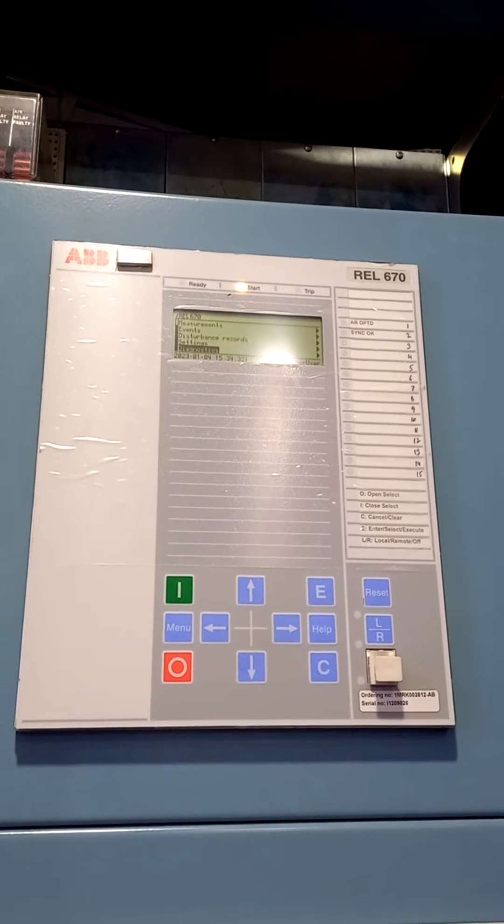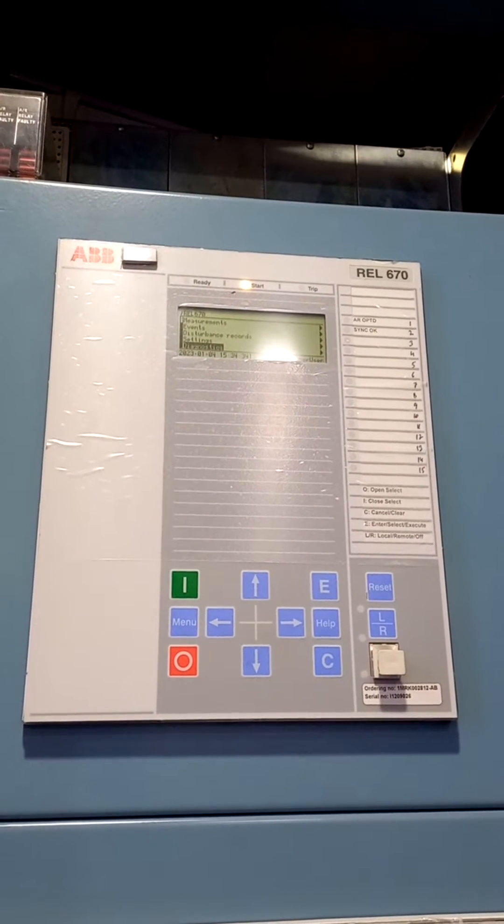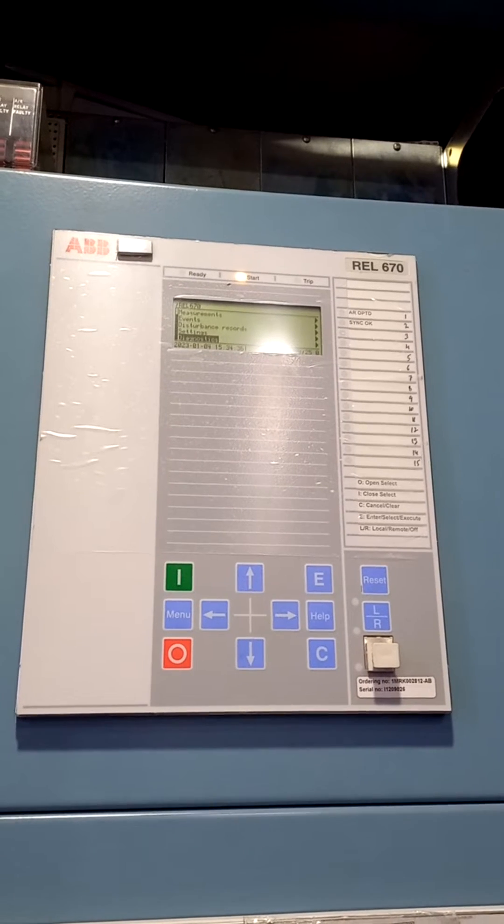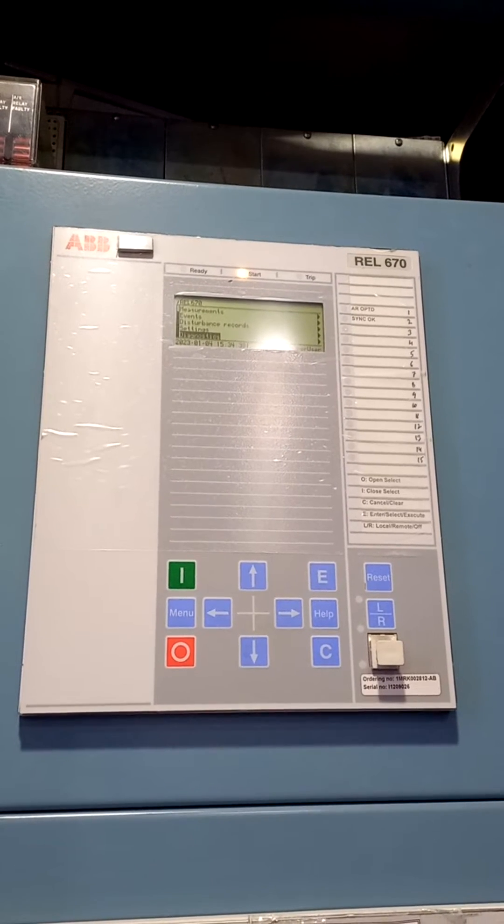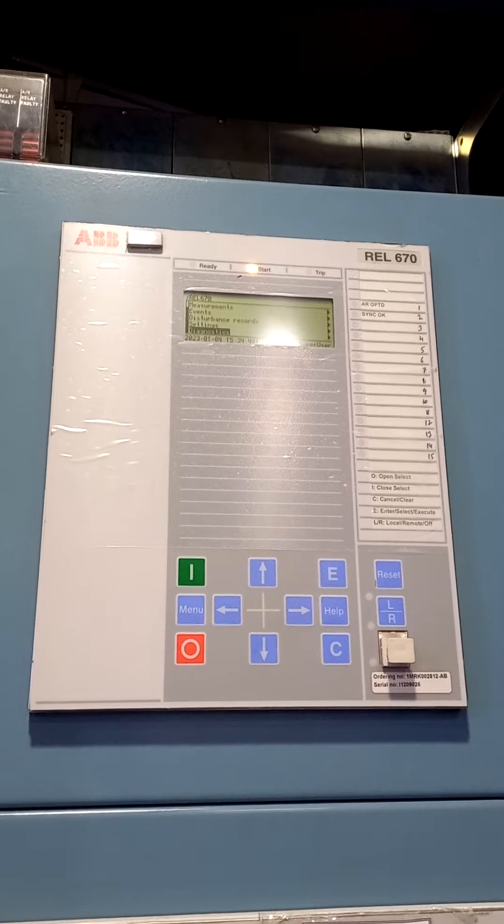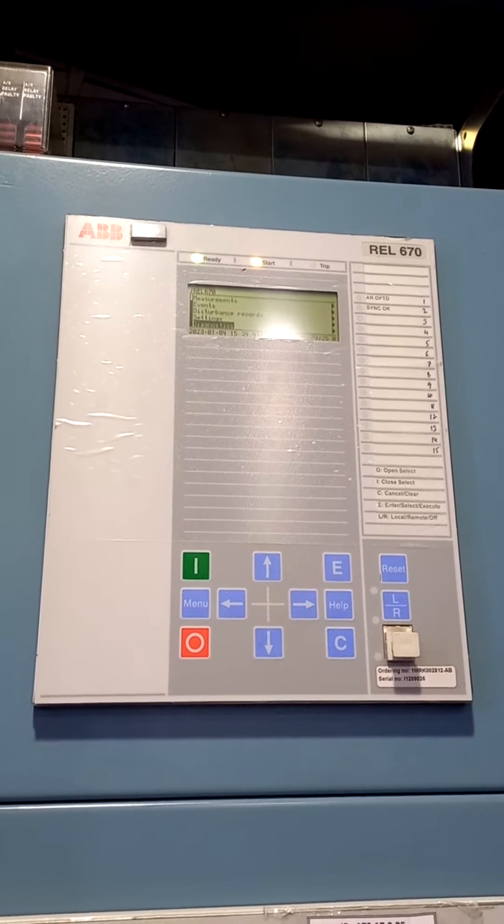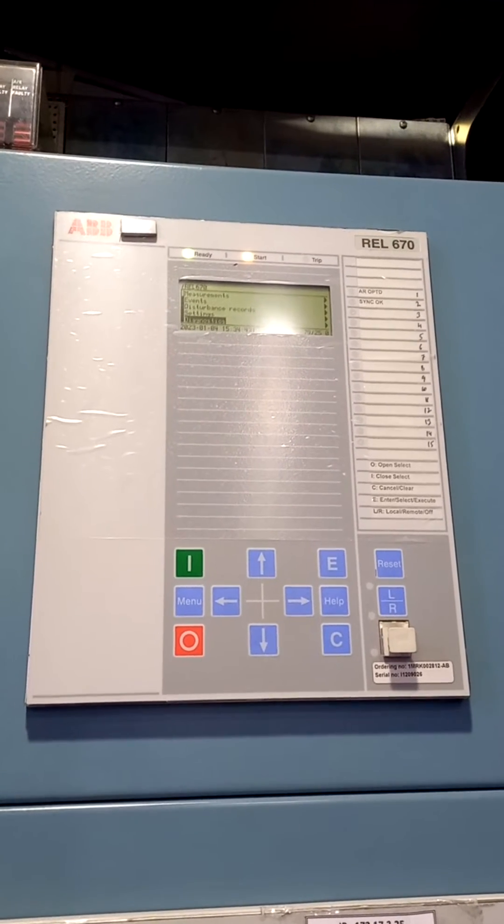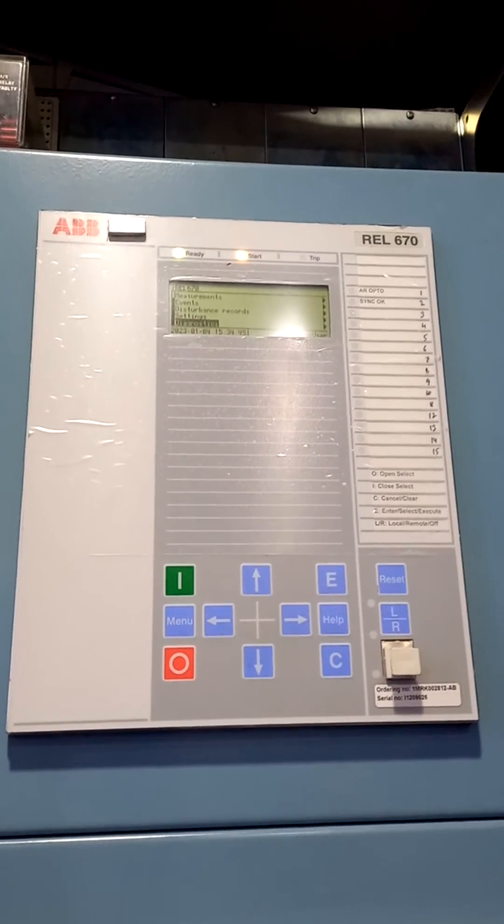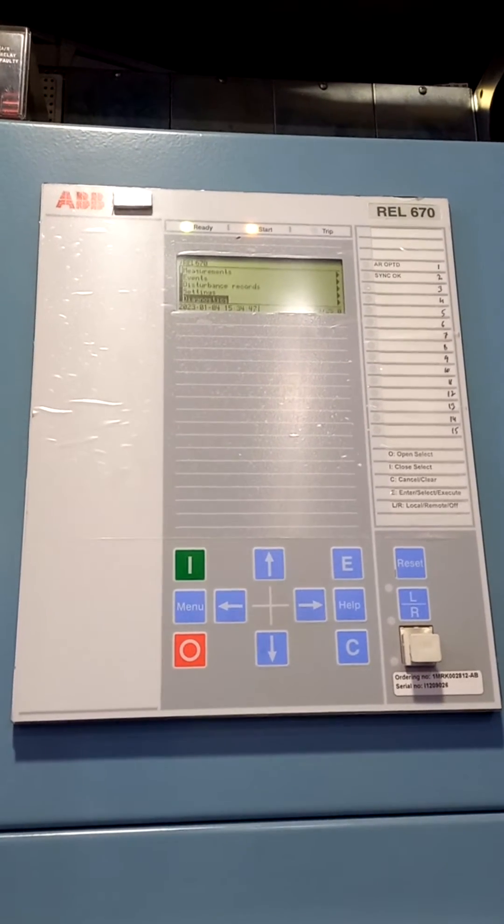Hi friends, today we will see in the REL 670 relay if this Ready LED is blinking continuously or flashing, what happens to the relay. It means any of the hardware is faulty in that relay.